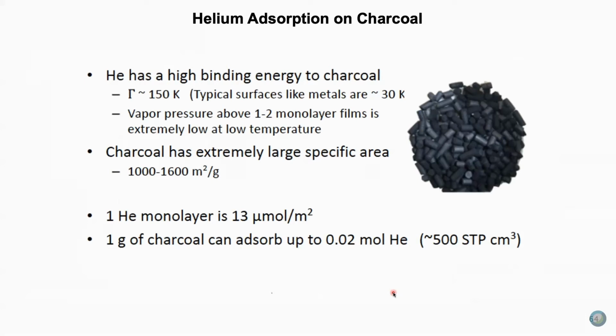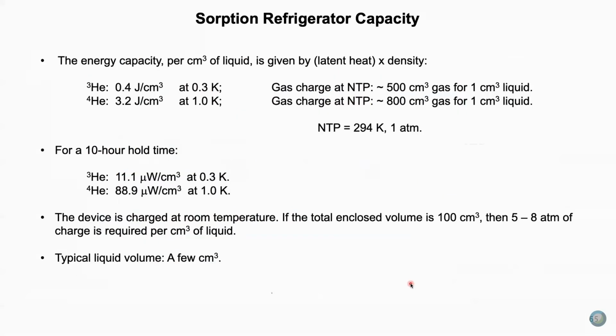So why do we use charcoal? Well, it has a very high binding energy relative to other things like metals. As a vapor pressure above 1 or 2 monolayer films is extremely low at low temperatures. Charcoal has an extremely large specific area. So you take 1 gram of charcoal, there's 1,000 to 1,600 square meters of surface area, which seems pretty incredible. 1 helium monolayer is 13 micromoles per square meter. And 1 gram of charcoal can absorb up to 0.02 moles of helium.